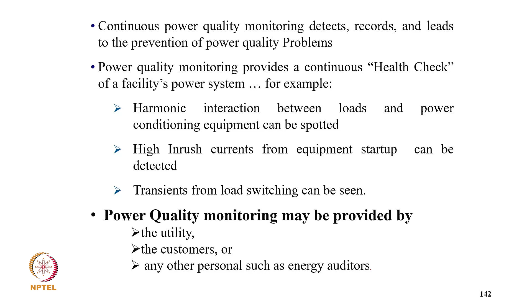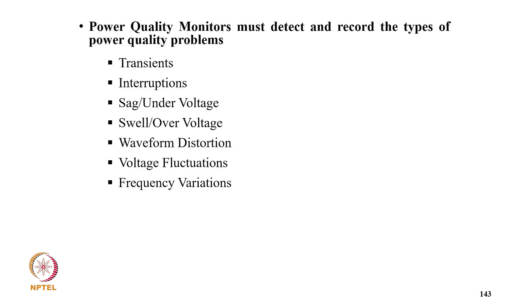Power quality monitoring may be provided by the utility, the customers, or any other personnel such as an energy auditor. The power quality monitors must detect and record the type of power quality problem: transient, interruption, sag (undervoltage), swell (overvoltage), waveform distortion, voltage fluctuations, and frequency variations. The objective of power quality monitoring is to quantify power quality phenomena at a particular location on electric power equipment, to diagnose incompatibility between the supply and the consumer load, to predict performance of the load equipment and select power quality mitigating systems, and to determine the choice of monitoring equipment and the method of collecting data at a particular location.